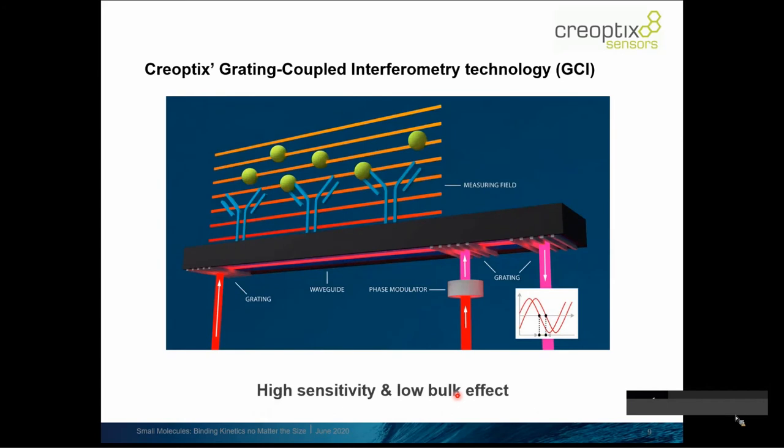Creoptix developed a proprietary technology called Grating Coupled Interferometry — GCI. The trick is coupling the measurement beam via a microfabricated grating that diffracts and couples light into the waveguide. A reference light beam is coupled via another grating into the very same waveguide, making the system very robust and stable. We read the phase shift — doing interferometry — with both beams traveling in the same waveguide, measuring interference with very high robustness and precision.